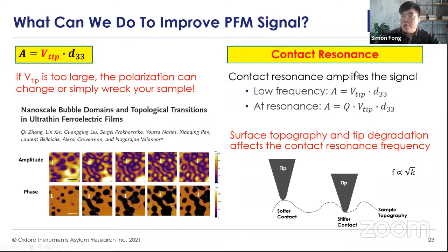In order to resolve these problems in contact resonance, we can track the contact resonance frequency. We use a technique called dual AC resonance tracking, or DART. In summary, what DART does is apply two AC voltages at the same time on the same probe, but with slightly different frequencies. Whenever the contact resonance of the tip and the sample changes, these two frequencies from the DART will detect the shift and correlate it back to the right resonance frequency.